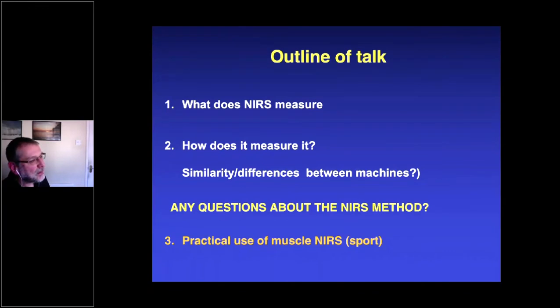In terms of where you put it on, well, it depends on the muscle group, of course. If you've got a big muscle group, it's less of an issue than if you're getting a small one. So if we're doing a continued study, we make a measurement. We always measure from the same distance. You'll see in the papers exactly where we make the measurement. If it's a measurement in a reasonable time frame, we make an indelible marker where we put the device, so we put it back on exactly the same place. It will certainly make a difference if you're off by a centimeter, because you're measuring a different part of the tissue.